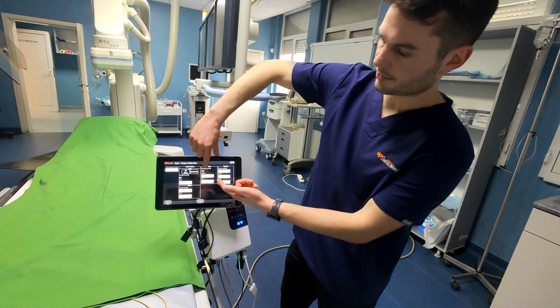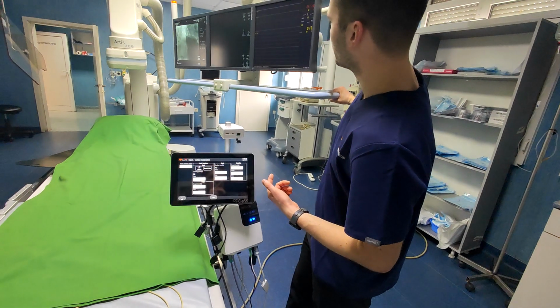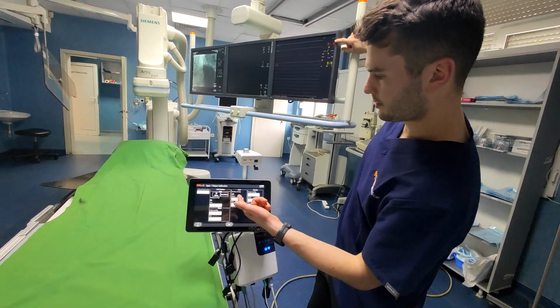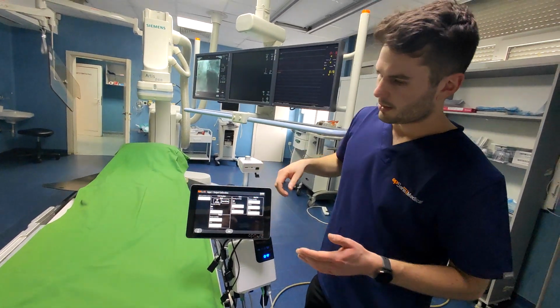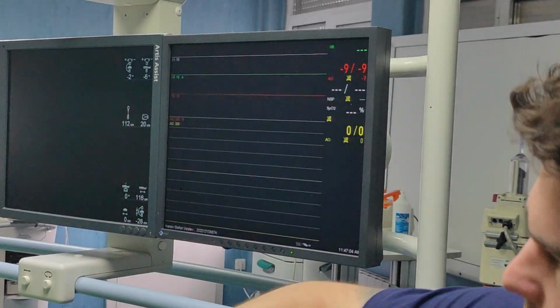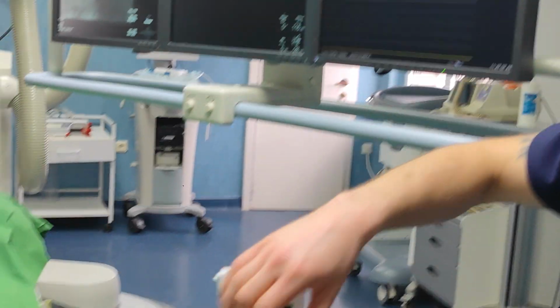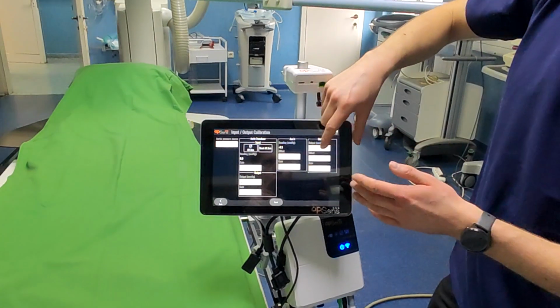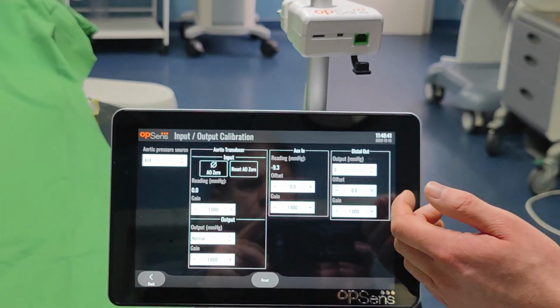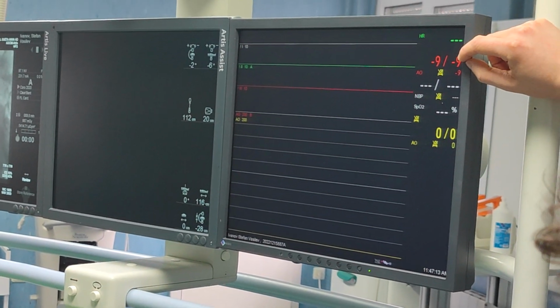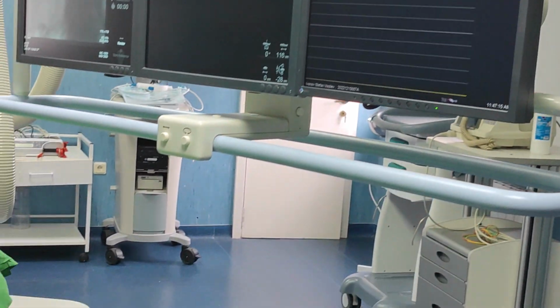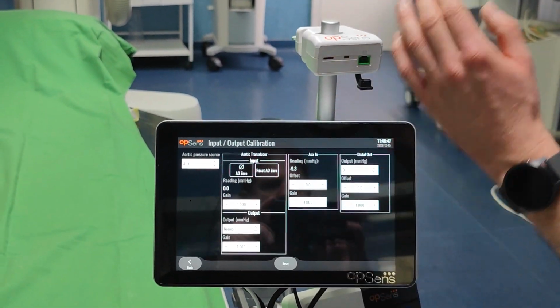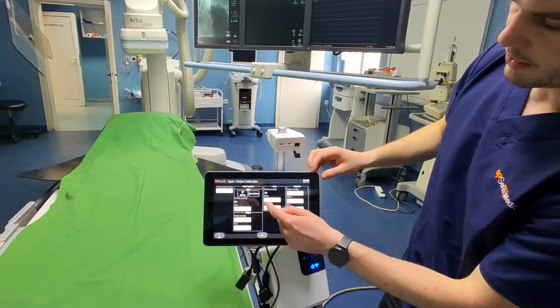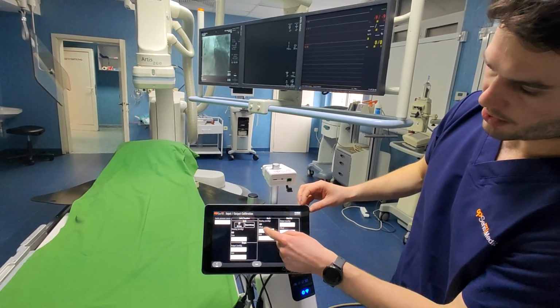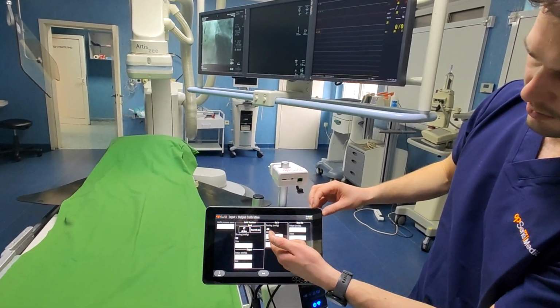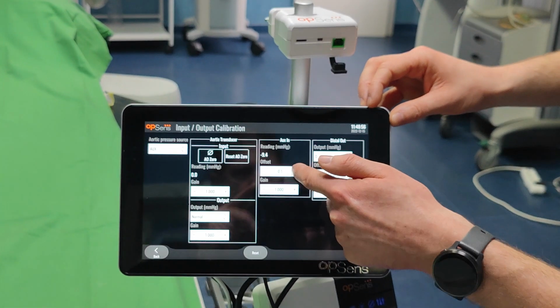Obviously we're not connected now, and their aortic signal is 9.3. So the idea is you want this to be the same as that. If it's not, you make adjustments. So set this to 0, wait for that to go to 0, and then with these you can offset the number so that this reads the same as that. So if you look, each one is 0.01, either up or down, and it will change the corresponding signal.